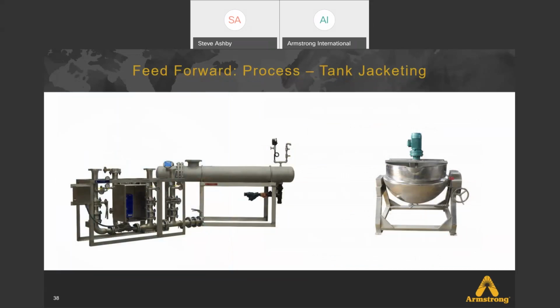So here are a few samples of process applications using steam to water heat exchangers, but requiring water temperatures to get to a set point quickly and then hold that temperature precisely. We talked about tank jacketing. Most of that is a closed loop application. The ReadiTemps can handle a closed loop application as well as a one pass to a process or a recirculated loop. So on demand, you would always have very precise water temperatures if you had a loop and you were feeding multiple applications.